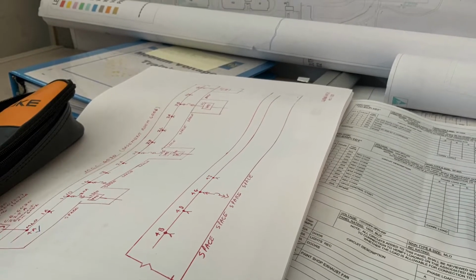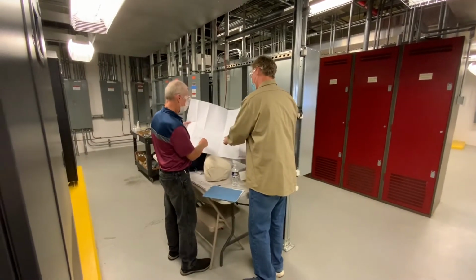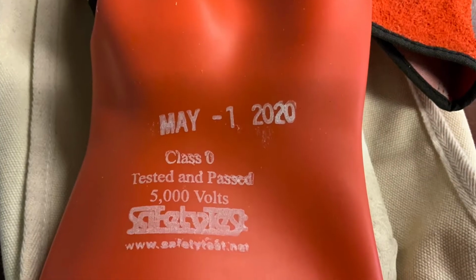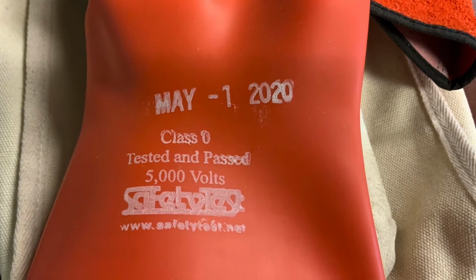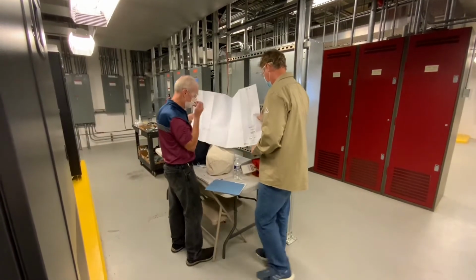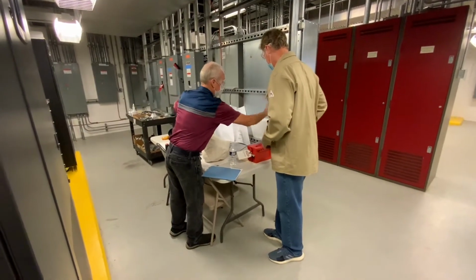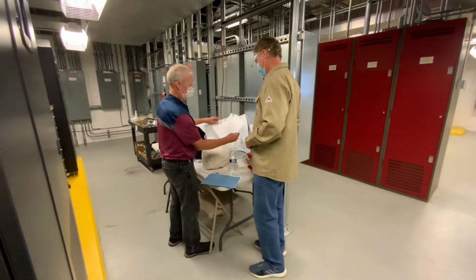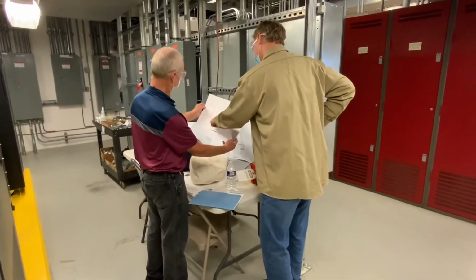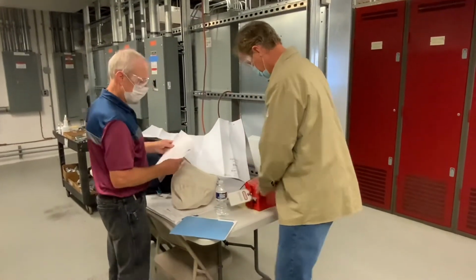1. A description of the job and the individual tasks. Identification of the electrical hazards associated with each task. A shock risk assessment, which identifies the voltages involved. The shock approach boundaries, both the limited and restricted, and the PPE required for shock prevention. An arc flash risk assessment, identifying the arc flash energy or incident energy an individual may be exposed to, the arc flash boundary, and the PPE required for the arc flash potential.